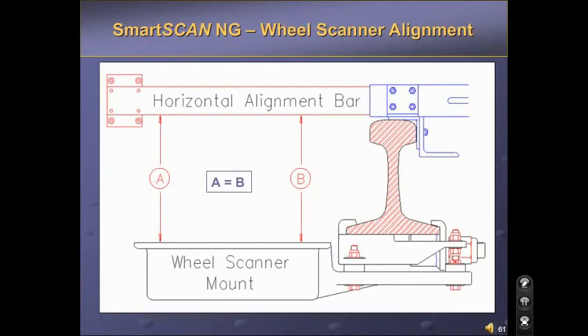Wheel scanner alignment is very simple. Extend the bar of the alignment fixture all the way out. Measure down from the front and back of the mount. These measurements should be equal. Use the same 2 bolts that the bearing scanner uses for horizontal adjustment. Vertical alignment is not necessary, as long as both hot wheel mounts are sitting between the gating transducers.